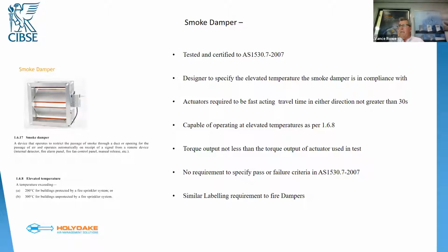Now, they've got to be capable of operating at elevated temperatures. There are two primary temperatures that are used in the testing standard. That's 200 degrees Celsius for buildings protected by a fire sprinkler system, or 300 degrees Celsius for buildings unprotected by a fire sprinkler system. Interestingly, AS 1530.7 does not have specific criteria for passing or failing that test. And the reason I bring that up is I had a consulting engineer put a report in front of me some time ago for a smoke damper, and the dampers in that report actually would have failed the test. And in fact, the testing authority that tested those dampers was not NATA certified to test smoke dampers. So again, it's quite critical that people understand the level of detail in these reports and follow those through.